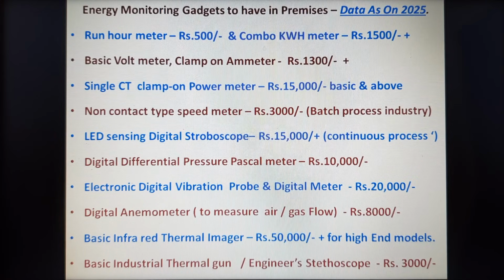Definitely this should show the loading, which is a critical component to determine the efficiency of any given system, whether it is a production machine or a utility machine. Then the basic volt and amps clamp-on ammeter costs only 1300, but definitely this will give an indication whether we are going in the right track as such. The single CT clamp-on power meter is around 15,000 plus. Definitely it will give you kilowatt, kVA, and it can even give harmonics also, such as the harmonics in the given VFD loads.